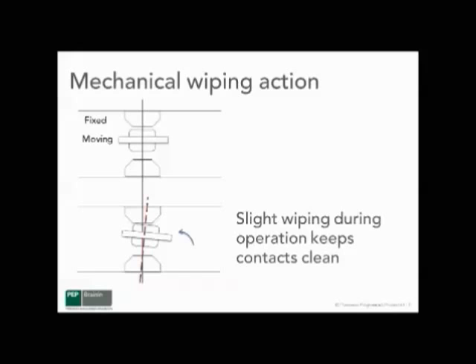Mechanical wiping action is another design consideration that can be utilized to keep the contact clean, especially during long durations of operation. You generally start with a fixed contact and a moving contact. The moving contact is on a flexible blade which allows it to rock or wipe during operation, helping to move any contamination on the surface to an area where it's not going to interfere with good electrical contact.